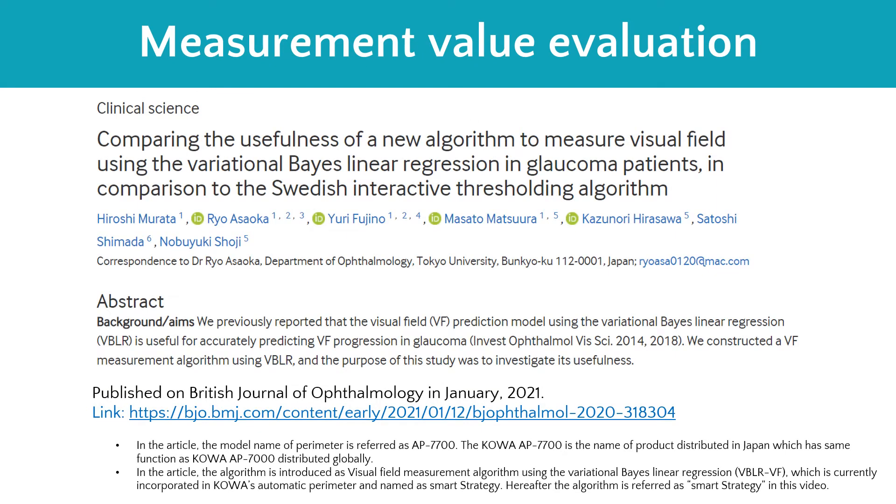Let's now discuss the study of actual measurement value evaluation using variational Bayes' linear regression on which our SMART strategy is based. This evaluation has been published in the British Journal of Ophthalmology. The study investigated our visual field measurement algorithm using variational Bayes' linear regression, with a methodology that included 122 eyes of 73 patients with open-angle glaucoma. It was concluded that variational Bayes' linear regression reduced test duration while maintaining the same accuracy as the SITA standard.